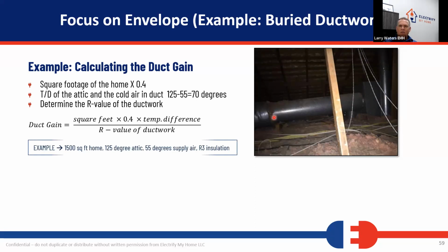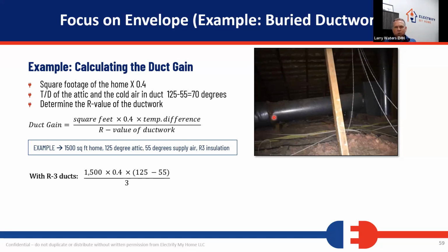So the way we do the math, we take that 1,500 square foot home, we've got 125, got our 70-degree temperature differential, R3 insulation. Take 1,500 times 0.4, and then we multiply that by the temperature difference, and then we divide that by the R value of the ductwork, and that tells us exactly how much energy our system is utilizing to keep those ducts neutral in the attic space. So in this particular scenario, this system is using 14,000 BTUs of its cooling capacity to keep those ducts neutral when the attic is only 125 degrees.